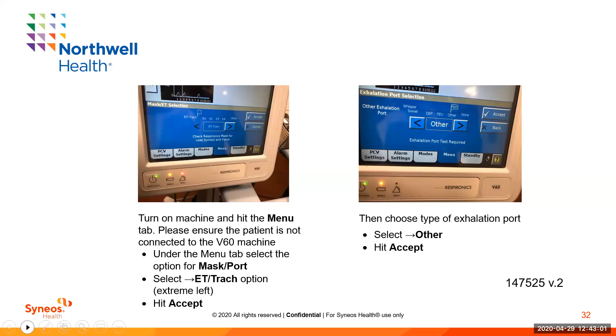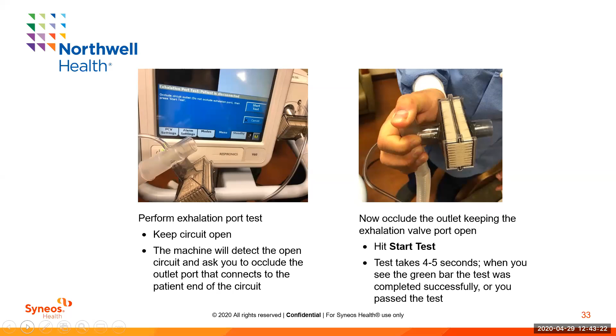And then there's an exhalation port test to make sure that the machine learns its initial leak. You occlude it, it does a little pressure testing. It measures the leak on the exhalation valve. And so now the machine is going to be sensitive to the patient that you'll put it on. Okay, next slide.